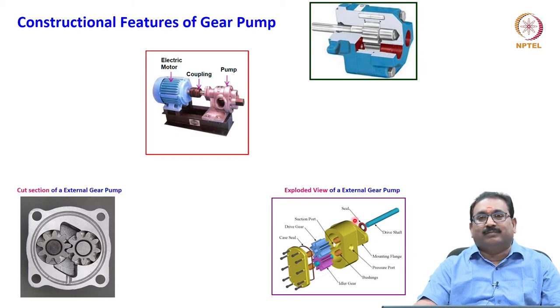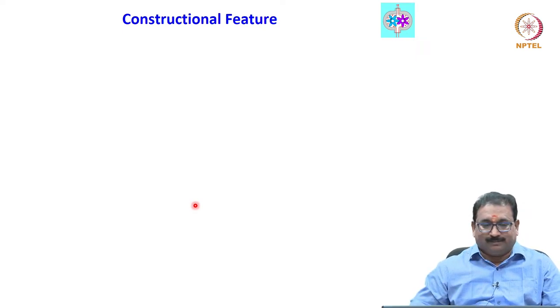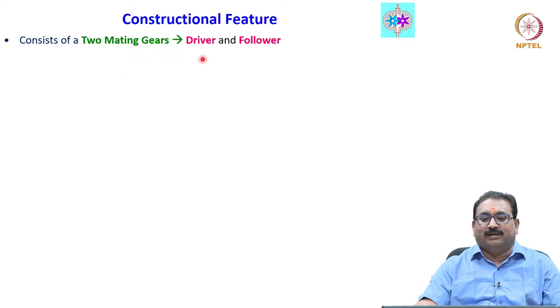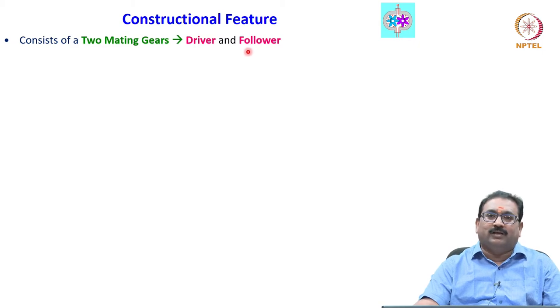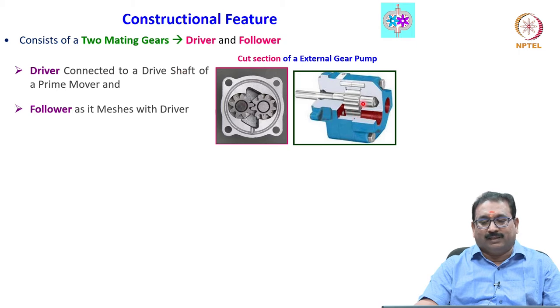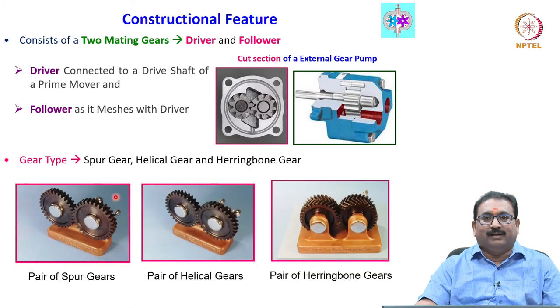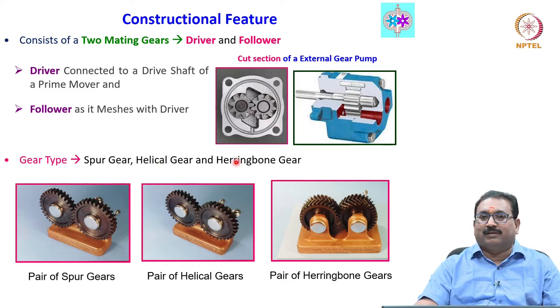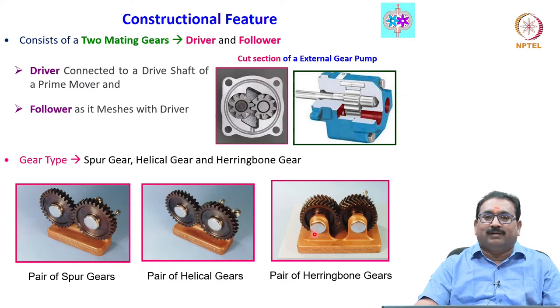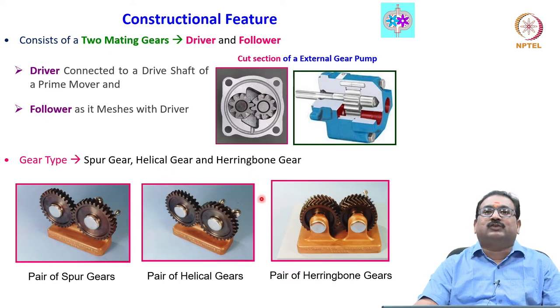Let us see the constructional features in detail. It consists of two mating gears — driver and follower. The driver is connected to the electric motor shaft through the coupling. The follower meshes with the driver. Different gear profiles are used in the pumps: spur gear, helical gear, herringbone gear. Based on the gear profile, different types of external gear pumps are available, each having its own advantages and disadvantages. A pair of gears is housed in the housing — the gear profile may be spur, helical, or herringbone type.